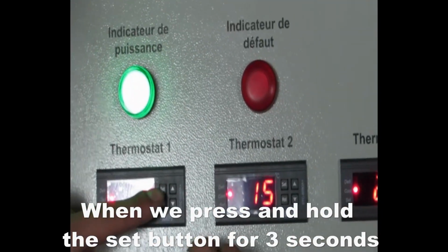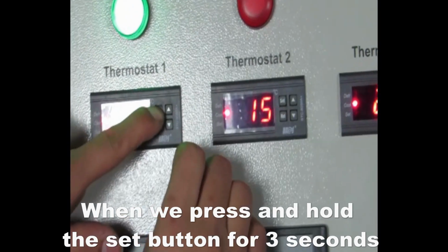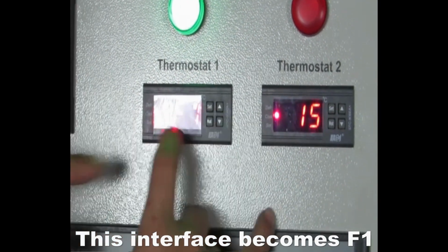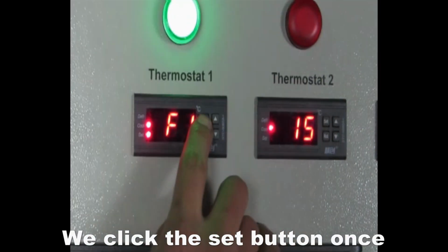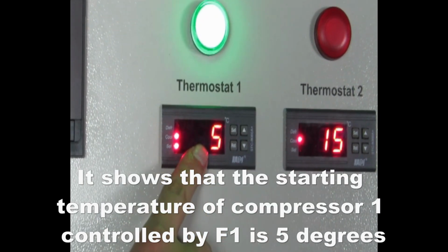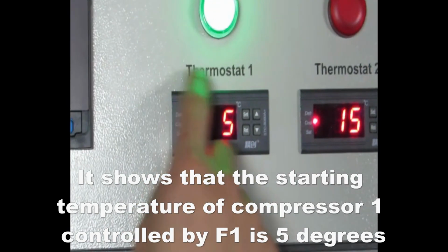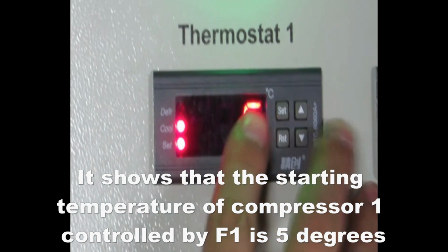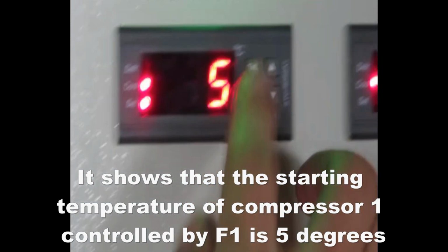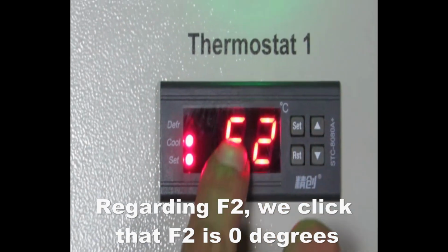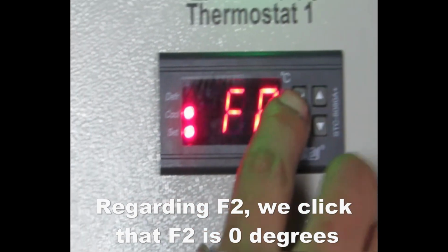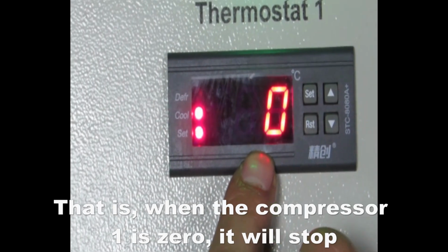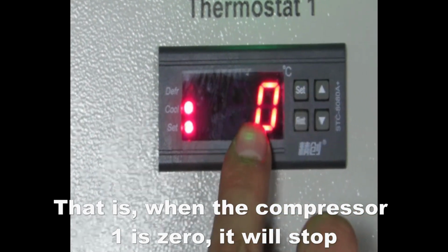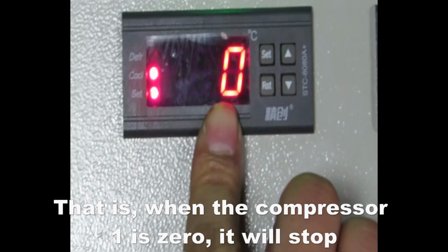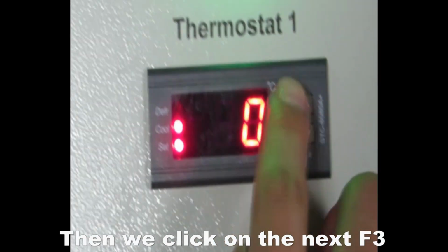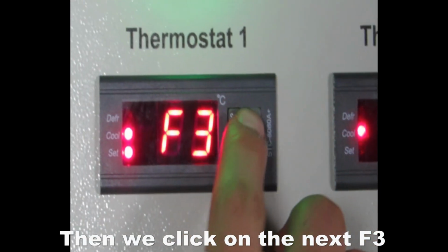When we press and hold the set button for 3 seconds, this interface becomes F1. We click the set button once. It shows that the starting temperature of compressor 1 controlled by F1 is 5 degrees. Regarding F2, we click and F2 is 0 degrees. That is, when the temperature reaches 0, compressor 1 will stop. Then we click on the next, F3.